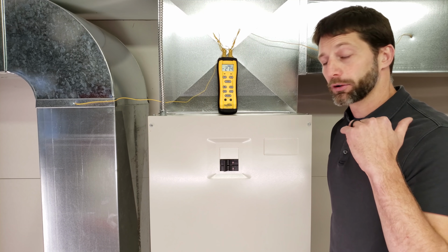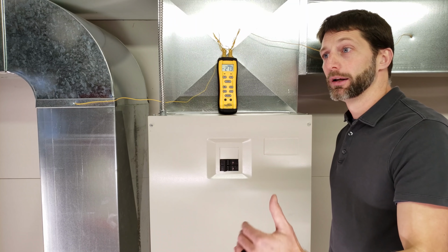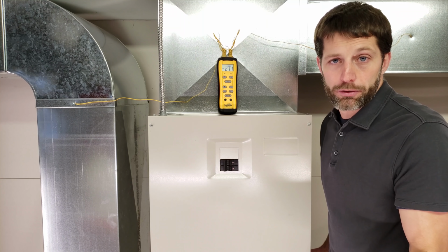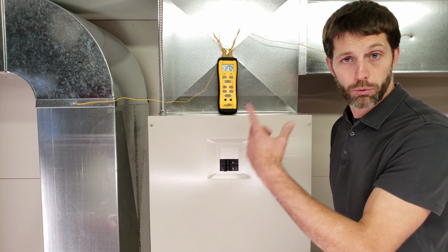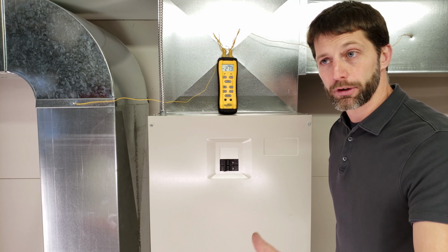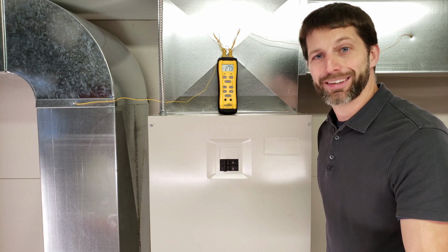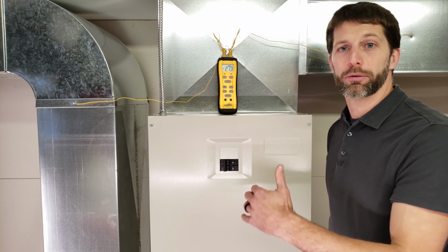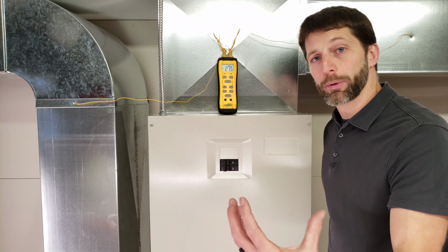It's going to depend on the outdoor temperature. If your outdoor heat pump is running and it's 50 or 55 degrees, it's going to have a much higher delta T at the indoor unit than when the outdoor temperature is maybe 30 degrees. Then your delta T at the indoor unit is going to be much lower. So it has to do with the amount of heat that the refrigerant is able to absorb outside.